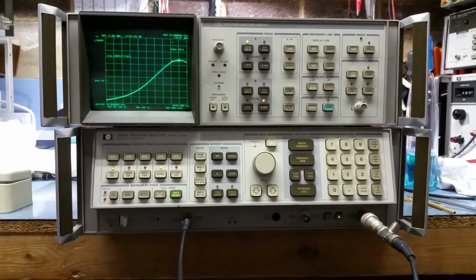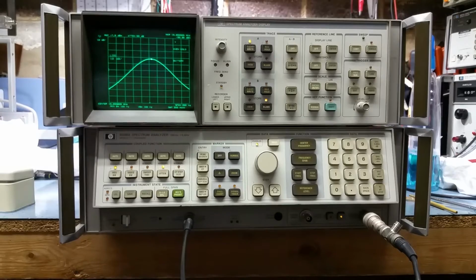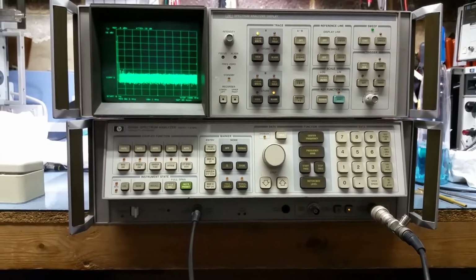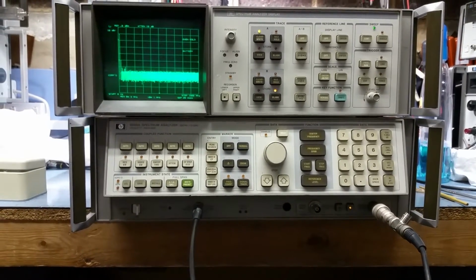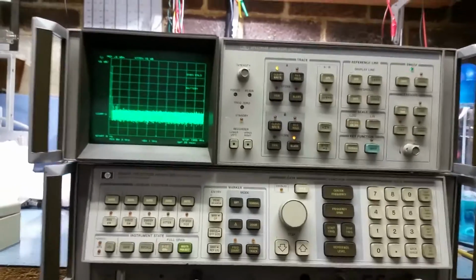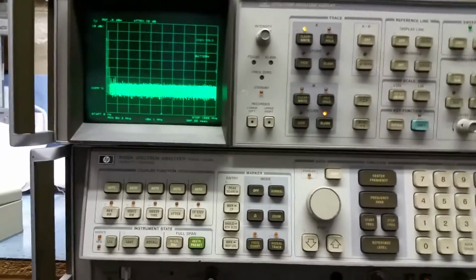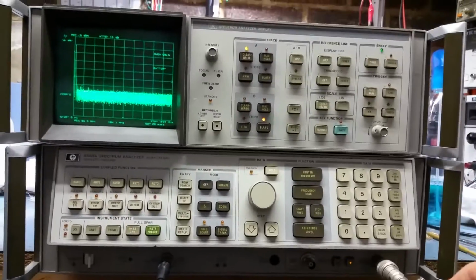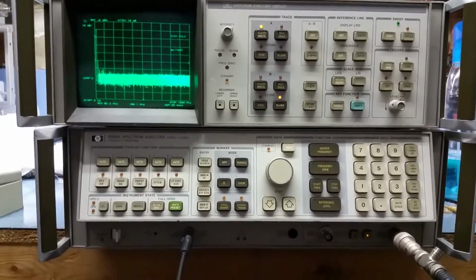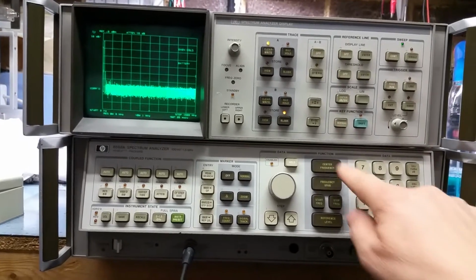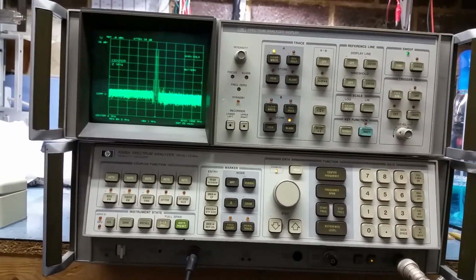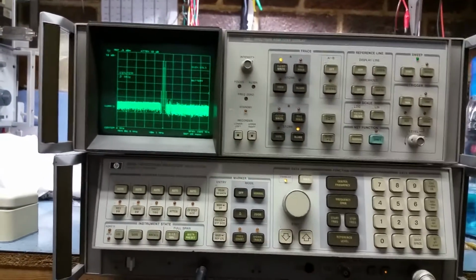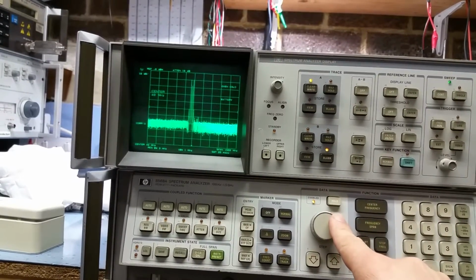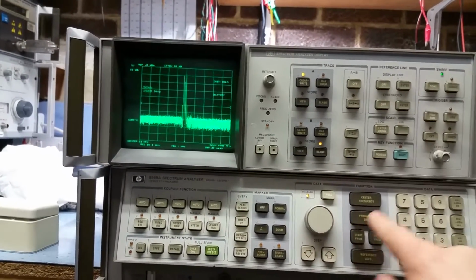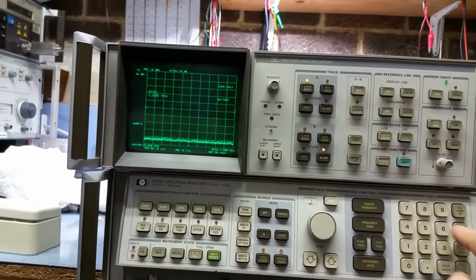Quite a bit of kit really for a late 70s design to be able to do a self-calibration run on itself. That's it, it's done it. Now there is a way you can recall the calibration it's put in, but it looks like it's absolutely fine. So we're running a 2 meg output into this, so if we recall center frequency 2 megahertz, and it's a comb marker. You can see the combs there in the center, and do a frequency span of 1 meg.